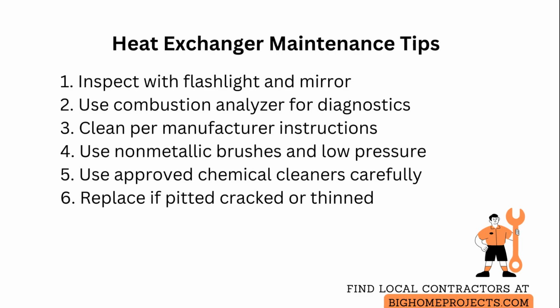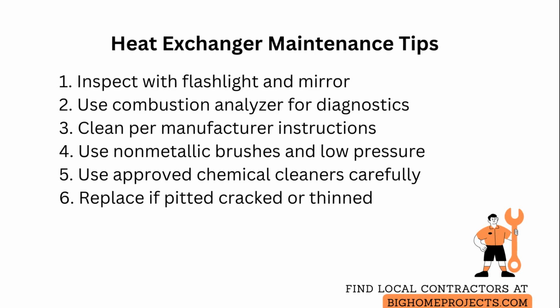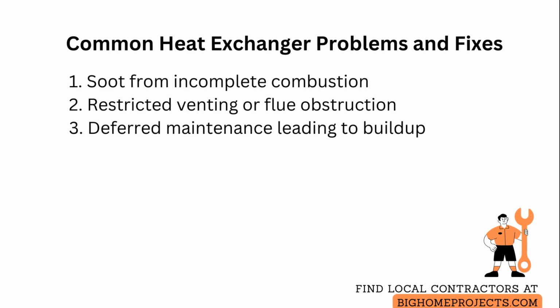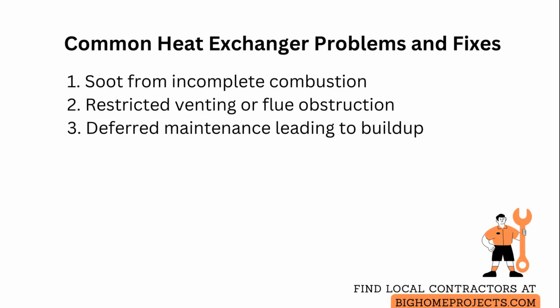If inspection reveals pitting, cracks, or thinning metal, replace the heat exchanger rather than attempting repair because structural failure can lead to hazardous gas leaks. Common issues include incomplete combustion or soot accumulation from poor fuel mixture, which clogs passages and raises temperatures. Correct this by verifying fuel pressure, burner adjustment, and performing a thorough combustion tune-up.